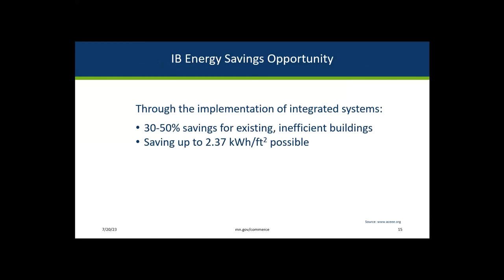A 2017 American Council for an Energy Efficient Economy report found that whereas an upgrade to a single component or isolated system can result in energy savings of 5 to 15%, an intelligent building with integrated systems can realize 30 to 50% savings in existing buildings that are otherwise inefficient. Savings can reach 2.4 kilowatt hours per square foot. The report examined a range of smart technology opportunities that included HVAC systems, plug loads, lighting, window shading, automated system optimization, human operation, and connected distributed generation and power.